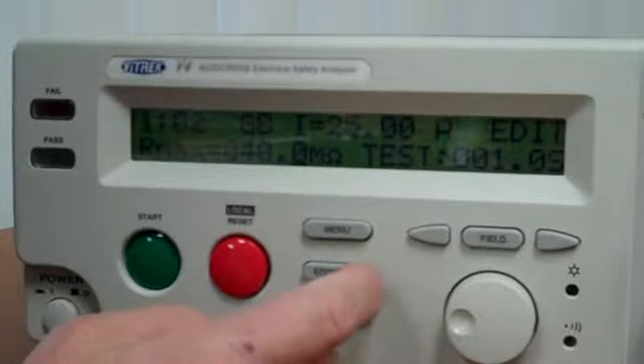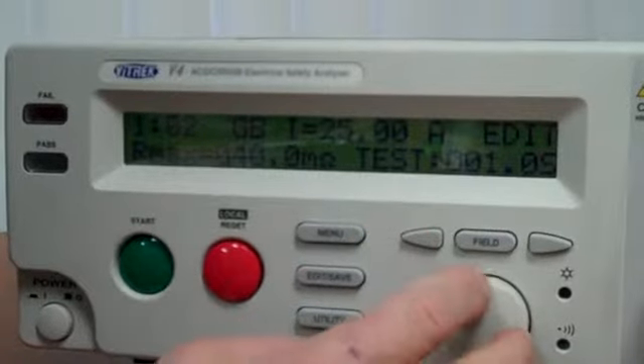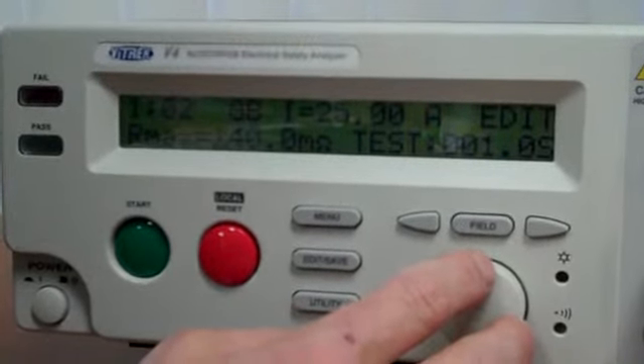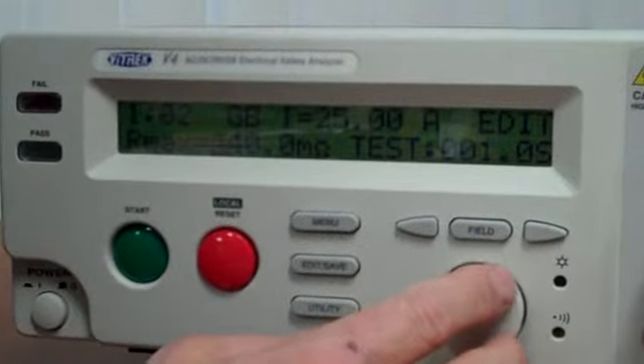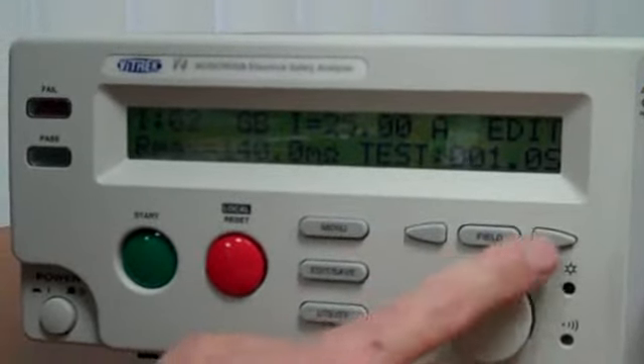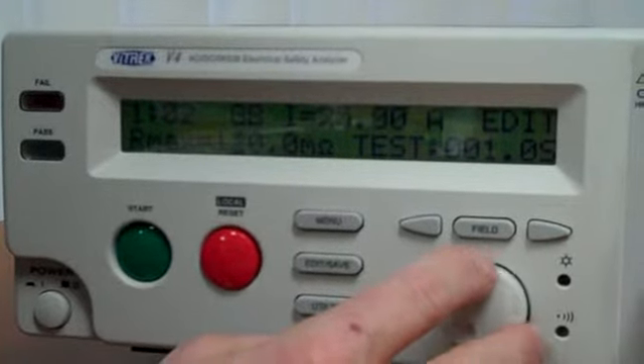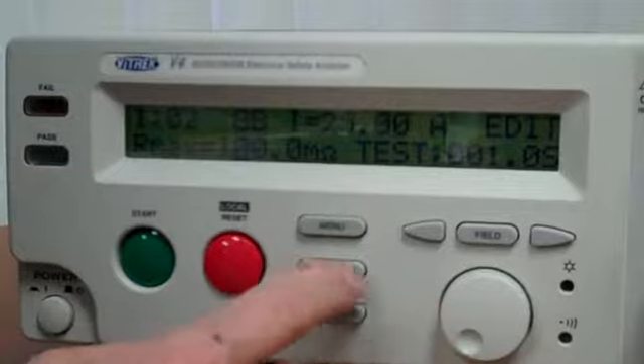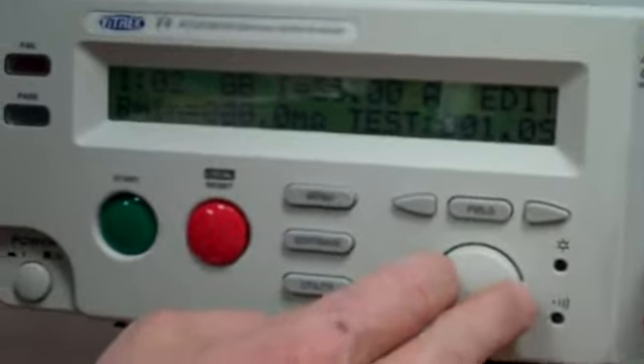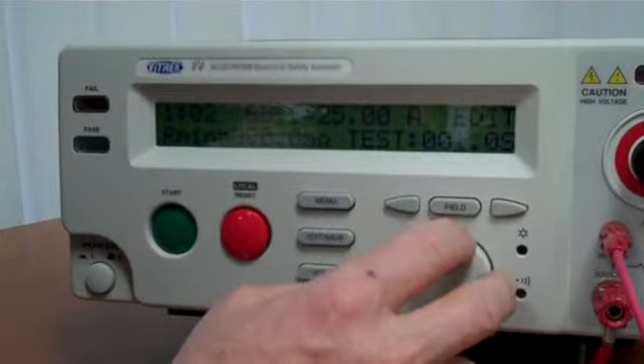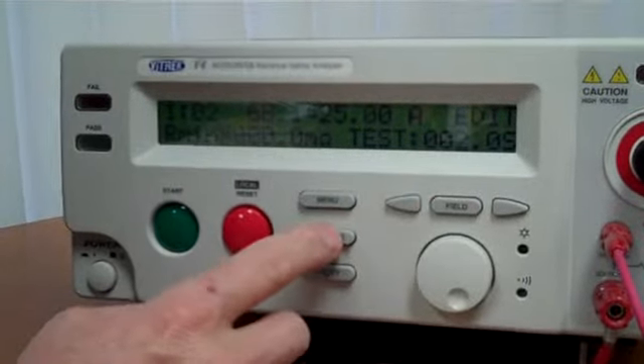Now we have the Imax, or the Rmax, which is the maximum resistance field. I recommend 100 milliohms. There we go. There's 100. Go to the next field, Rmin. I'm going to recommend 0. And then we have a test time. Let's do a 2-second test. And save. Okay, we've just done an AC withstand test followed by a ground bond test.